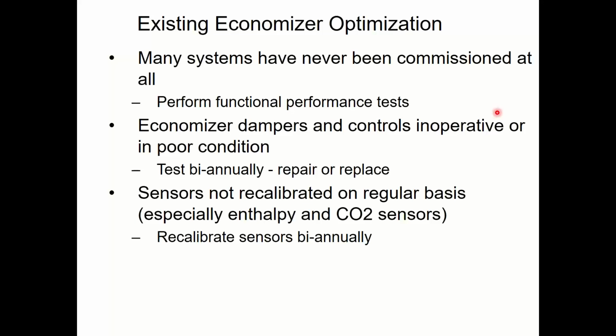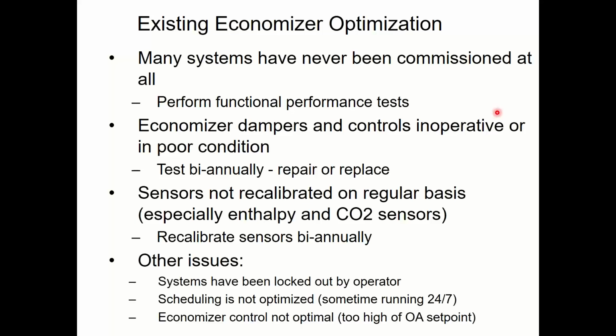So sensors, we talked about CO2 sensors being much better from a calibration standpoint. I joked about the enthalpy ones that we used to make out of horsehair. We literally did. There was horsehair in there. And as it got more humid, the hair would deflect more and click the relay. Just like, well, I don't have hair, but like other people that have hair, their hair gets more curly or less curly depending on the humidity. Same kind of idea worked there. Nobody uses that anymore. It's all solid state electronics. It's much more reliable. I would still check the calibration of them, just like I do with the temperature sensors, but you probably don't have anywhere near the problems you used to have.